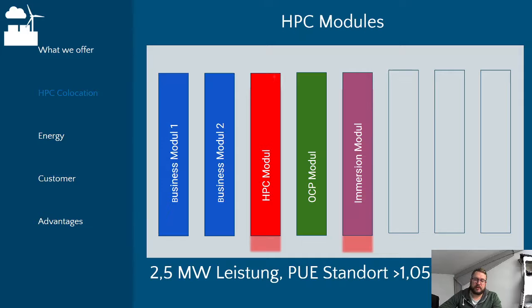The HPC module is direct-to-chip water-cooled, which I'll talk about in more detail. Another specialized module is OCP, or air-cooled HPC, up to 20 kilowatts per rack, focused on air-cooled high-density workloads. We also have another exciting technology planned: an immersion-cooled module, where servers run in big tanks full of oil. I'll have details on this a bit later.